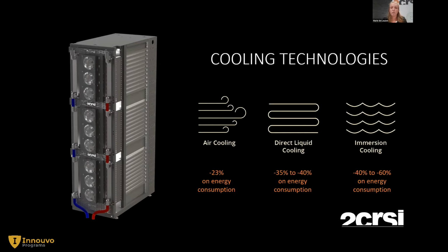One is immersion, where you have servers that are fully immersed in a tank filled with a dielectric fluid. So you have servers that are set vertically in a very large tank. And the second one is what we call direct liquid cooling, which means that a fluid in a pipe goes through the servers in order to cool them.